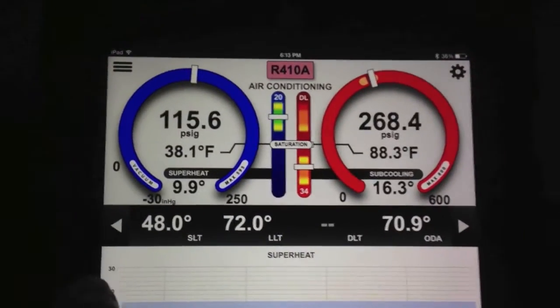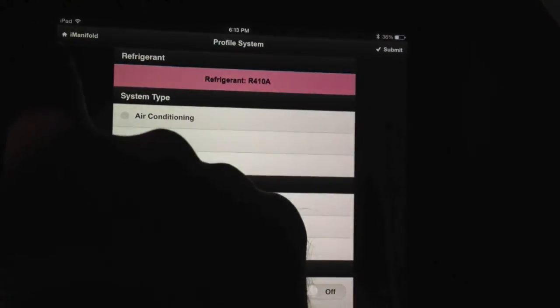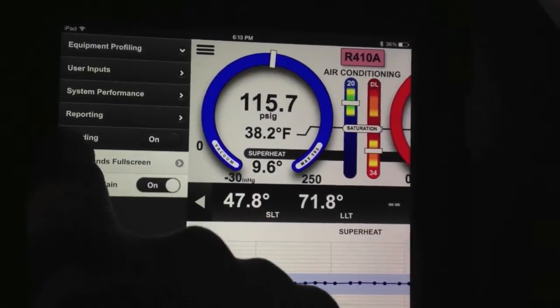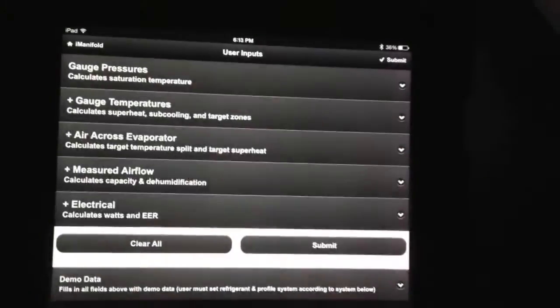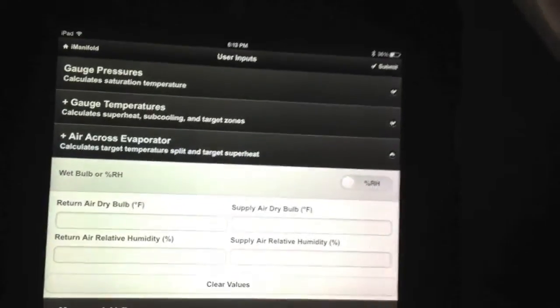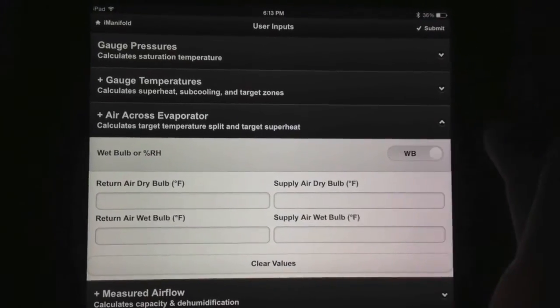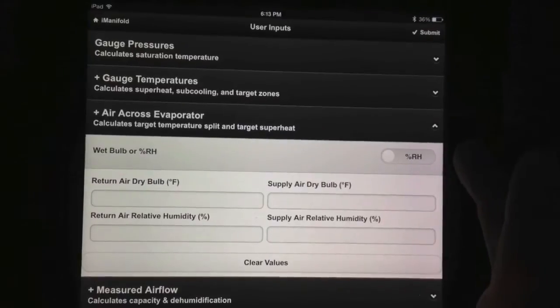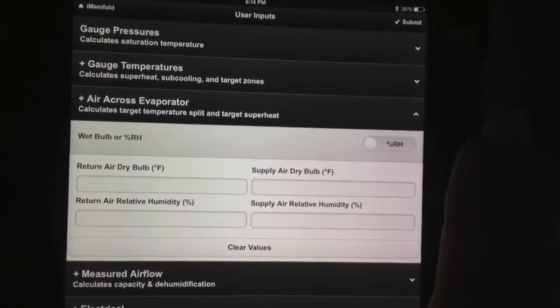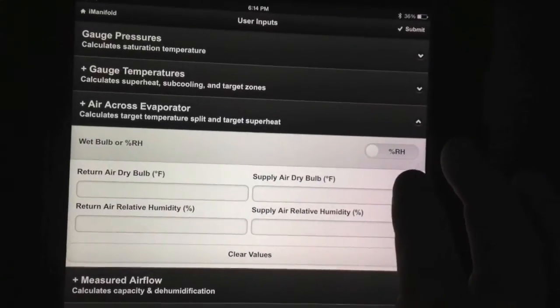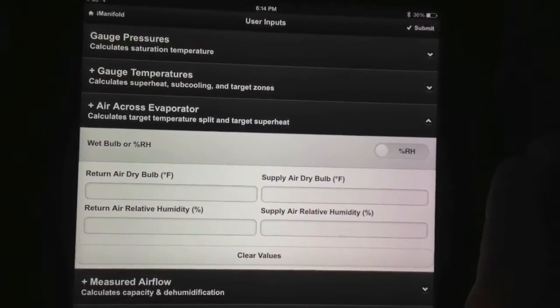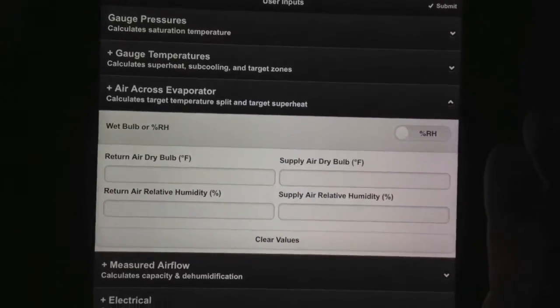I'll go back over to user inputs for a minute. Going to close the profiling and go to user inputs, then air flow across the evaporator. One thing you'll notice is that we've added a slider for wet bulb or relative humidity — you can just touch it and switch between entering wet bulb temperatures or relative humidity. I prefer relative humidity because wet bulb is a calculation, so it's more precise to use relative humidity and dry bulb temperature.